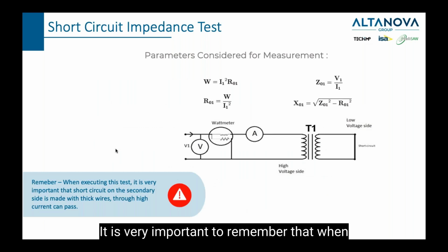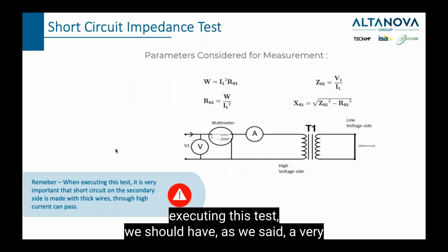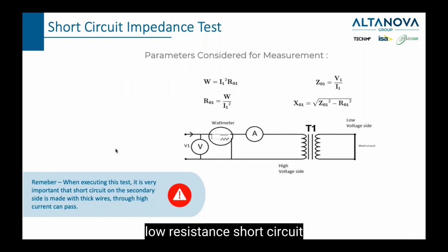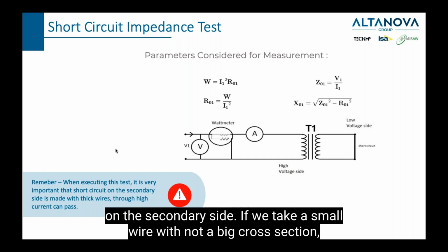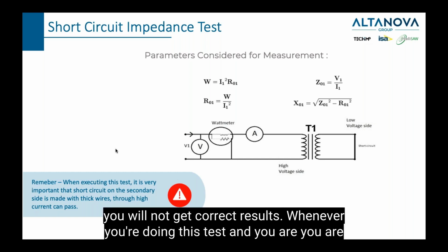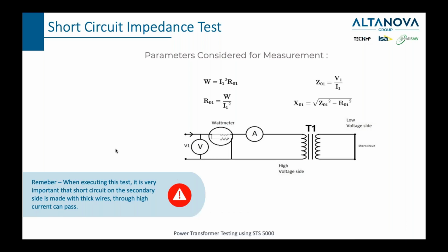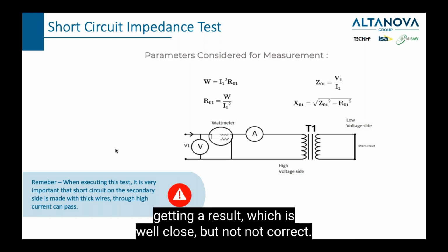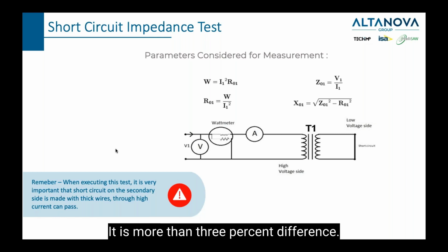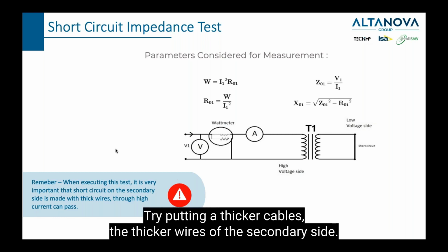It is very important to remember that when executing this test, we should have, as we said, a very low resistance short circuit on the secondary side. If we take a small wire with not a big cross section, you will not get correct results. Whenever you're doing this test and you are getting a result which is close but not correct, more than 3% difference, try putting thicker cables, thicker wires on the secondary side.